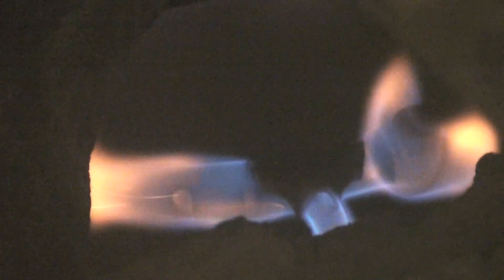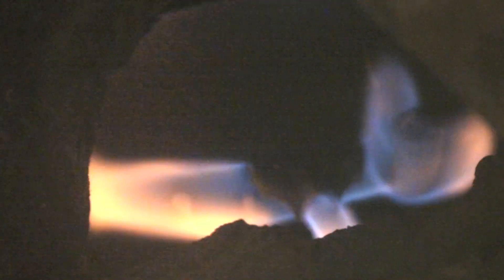Here's a look at the pilot. The piezo igniter spark gaps are on the left, and the thermopile is on the right. You can see that flame pretty much envelops the thermopile — that's the way it should be.